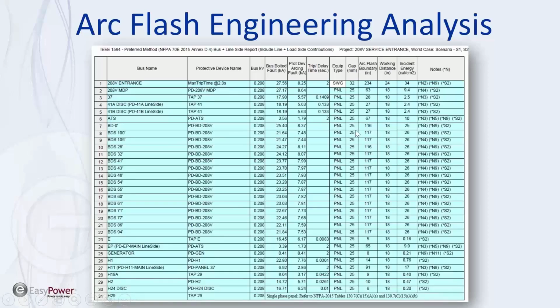You'll notice where there's lower levels, so 0.14, this is from this tap, it's at 2.5 calories, so it's going to show a much lower arc flash level versus the 2-second ones that are 25 and 26 calories. And then the arc flash boundary, of course, is going to reflect that time element as well. So this is all data that's on your arc flash information that's available on the arc flash study.